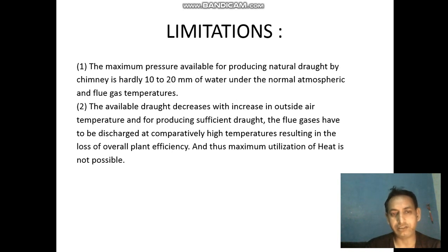Now the limitation is that it creates a draught of only 10 to 20 mm of water column at normal atmospheric condition and flue gas temperature. The draught decreases with the increase in outside air temperature.